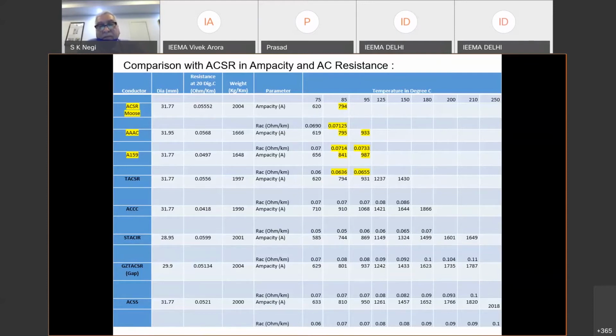So here then it's a well-established fact that a 400 kV line, even in load dispatch centers, is limited to the extent of 400 or 450 amps, and it is not loaded beyond the surge impedance loading, and surge impedance loading of the 400 kV line itself is about 500 megawatt. So we have to think of a conductor which can carry better megawatt with the same sag and same tension positions in the existing tower or a new tower design.